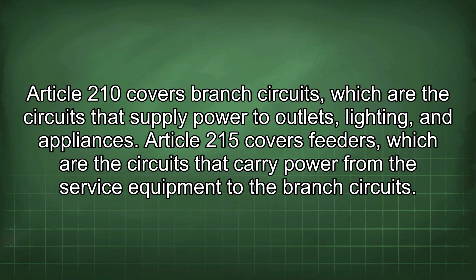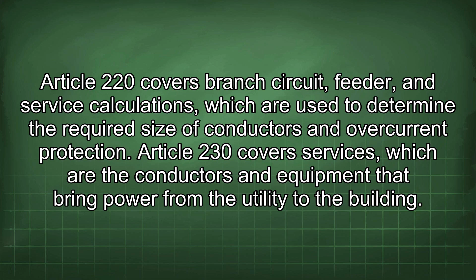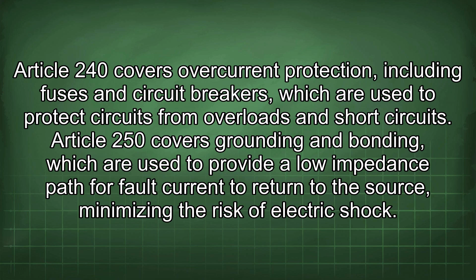Article 220 covers branch circuit, feeder, and service calculations, which are used to determine the required size of conductors and overcurrent protection. Article 230 covers services, which are the conductors and equipment that bring power from the utility to the building. Article 240 covers overcurrent protection, including fuses and circuit breakers, which are used to protect circuits from overloads and short circuits. Article 250 covers grounding and bonding, which are used to provide a low impedance path for fault current to return to the source, minimizing the risk of electric shock.